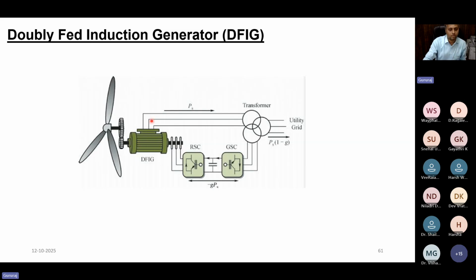So there is a 50 hertz component which will be directly flowing through the grid, and there is an excess component of energy also being seen at the stator side. That needs to be evacuated through some other channel, and that channel is the rotor side. Here, the power flows from the machine to the rotor side converter, and the rotor side converter will dump this power on the DC link capacitor, because of which the DC link capacitor voltage shoots up. You need to maintain this voltage at the nominal value so that you observe this transient and feed it to the grid.